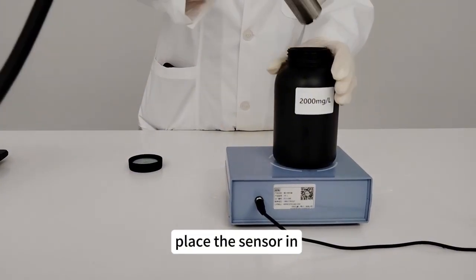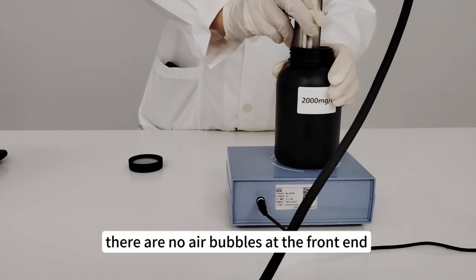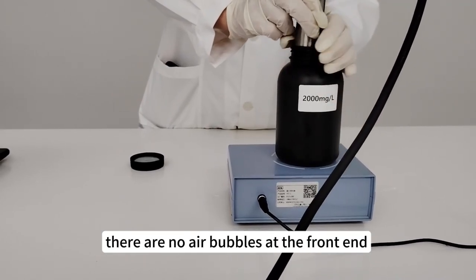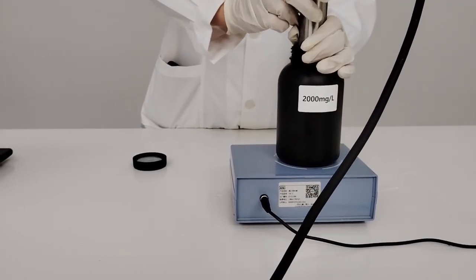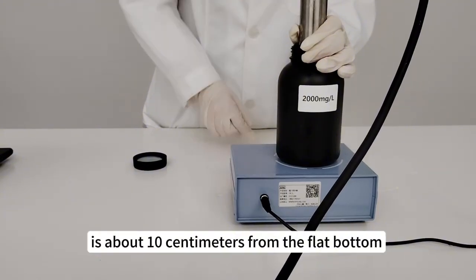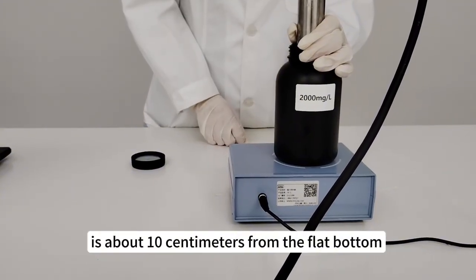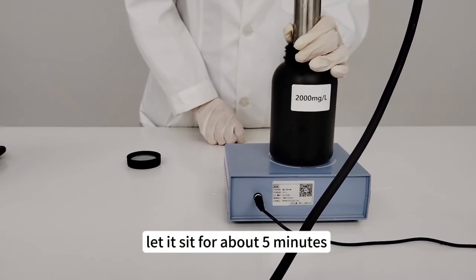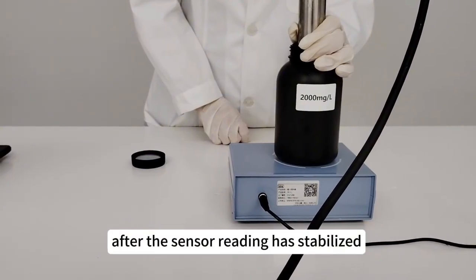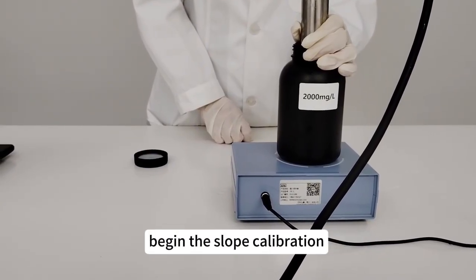Place the sensor in. Shake it to make sure there are no air bubbles at the front end. The front end of the sensor is about 10 centimeters from the flat bottom. Let it sit for about 5 minutes. After the sensor reading has stabilized, begin the slope calibration.